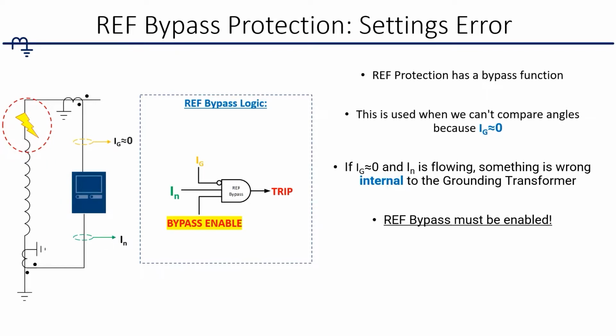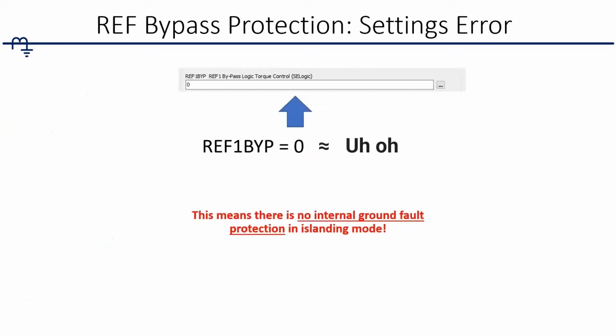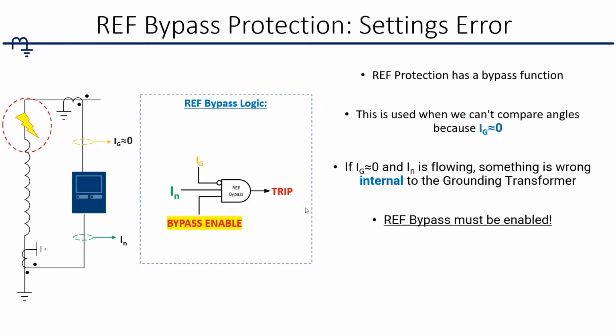And there's some reasons why there is logic to turn it on. There's a whole explanation behind that when they're used in other systems, such as auto transformers with secondary breakers on them. But the point in this exercise is that you have to actually turn the thing on for it to work. And we started digging into this logic and we said, okay, well, I wonder what happened here. So here's the REF bypass logic, and it was set to 0. So that was a pretty big uh-oh moment for us, where we said, okay, that's a pretty major settings error.